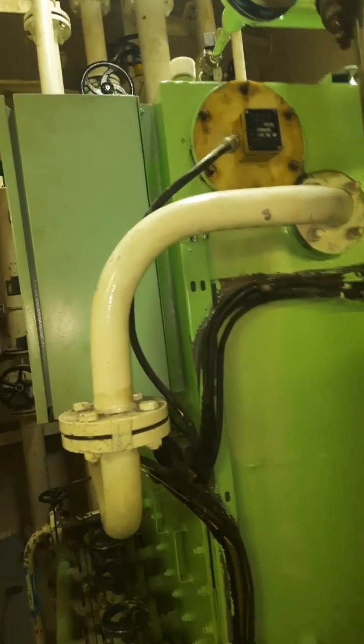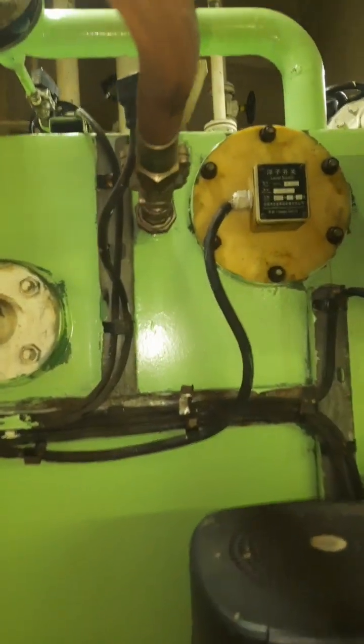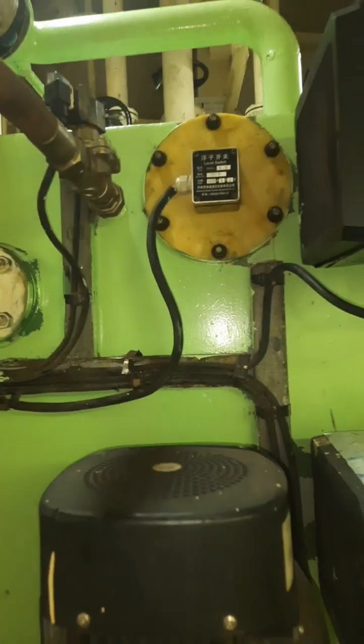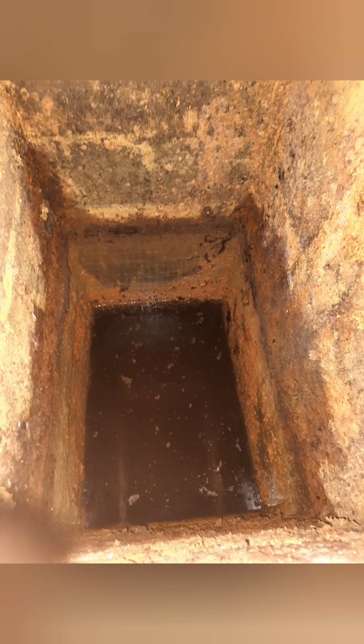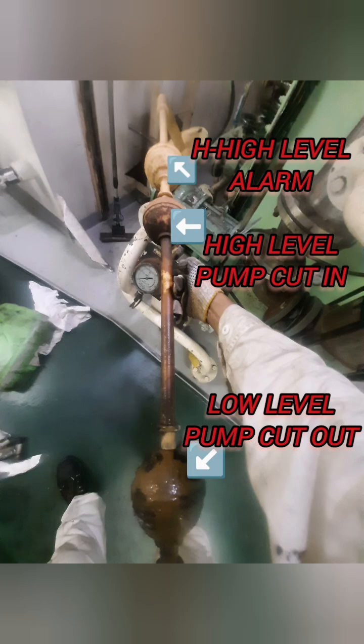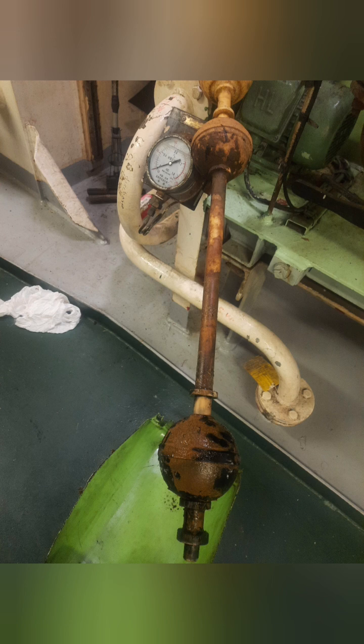And if the topmost float is lifted, it will trigger the alarm — the high level alarm. This is the basic testing of the sewage treatment plant, which we will now demonstrate on an actual sewage treatment plant. You can see the float switches on this plant. Inside the last chamber it looks like this, and the water is filled up in this fashion. We have taken out the float switch — you can see the three floats: the topmost is the high level alarm, the middle is the high level, and the bottom most is the low level.